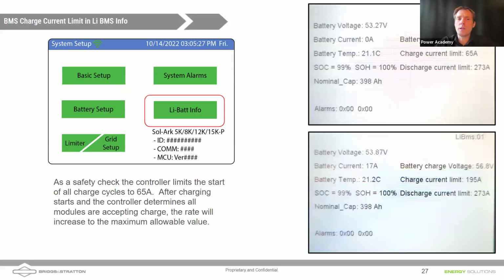Once we've told the inverter that we've got a communicating battery, there's going to be an extra button that appears on that main settings menu, and that's lithium battery info. This is information that's communicated directly from the batteries. So what you should see when a battery has not yet initiated a charge cycle is that it's requesting 56.8 volts, but no matter how many batteries you have connected, it's actually just going to show you it's requesting 65 amps of charging. And that's to ensure safety of the battery.